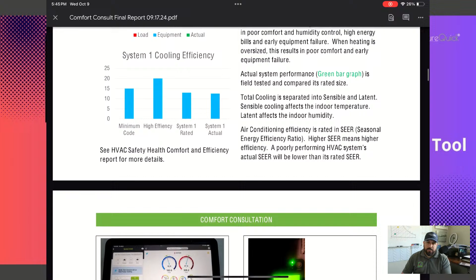Now let's pause right here real quick - I want to go back to those bar graphs. Right there, you see that HVAC system heat load versus equipment versus actual. Here we get to visualize what the load calculation called for, what the equipment is rated for, and what it's actually doing, divided into total, sensible, and latent. If I can run the heat, I will - not a lot of times in my climate, but that's a good visual to see. All those bar graphs should be pretty close to one another. If one of those colors is really high or really low, we've got a sizing issue.